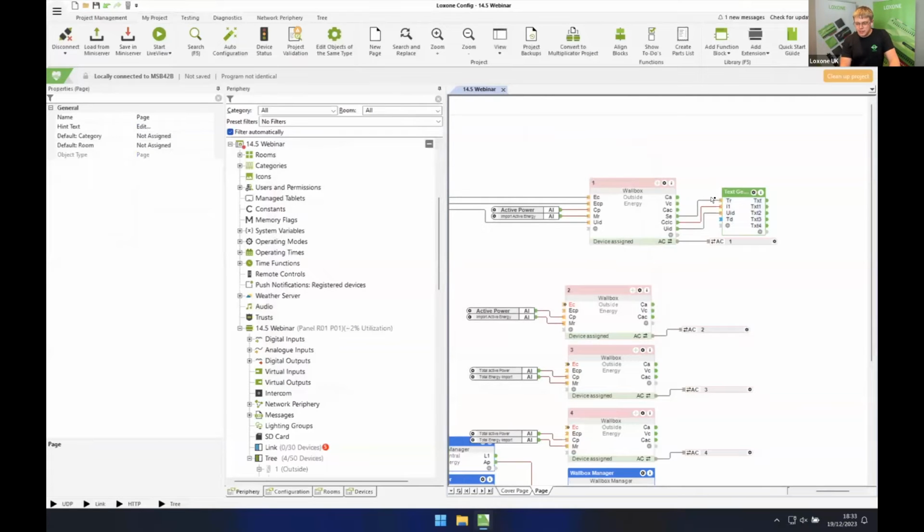So then when session ends, we are going to be taking the username of the user who's presented their NFC fob. We're then going to be taking the charging costs from that session that they've just had. And then we could take the text which is created and send this to a log file. Now, this log file could be a CSV file stored locally on the mini server. It could be a syslog server or something like that that you have set up on the customer's site, or they could be reporting it to a web page with basic authentication, somewhere where the person who's responsible for generating the invoice can grab that data.